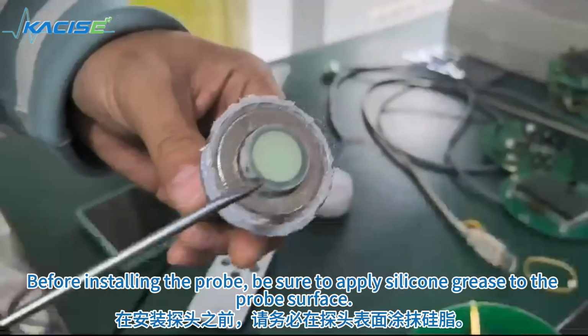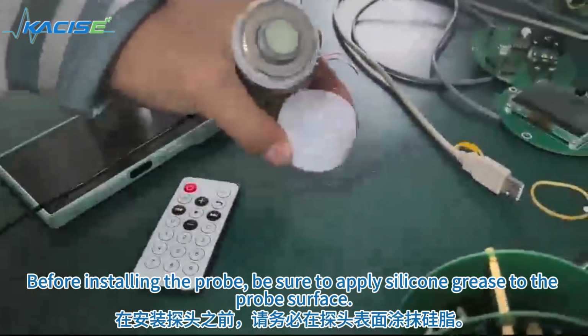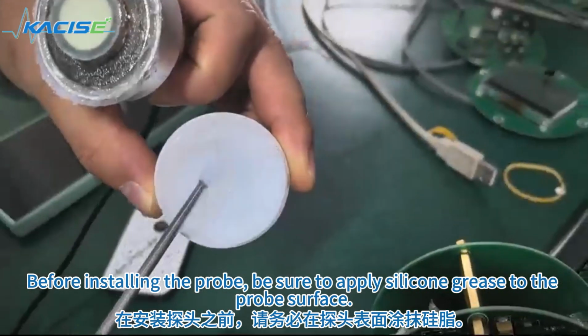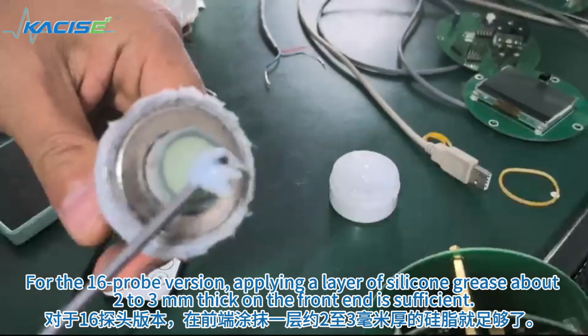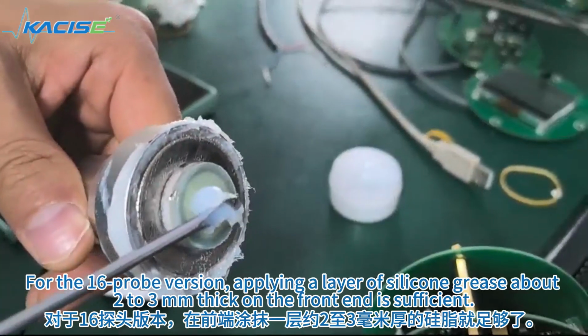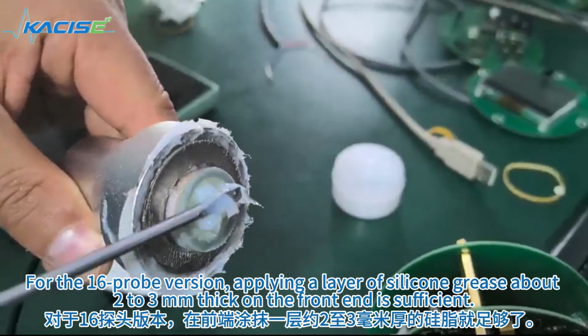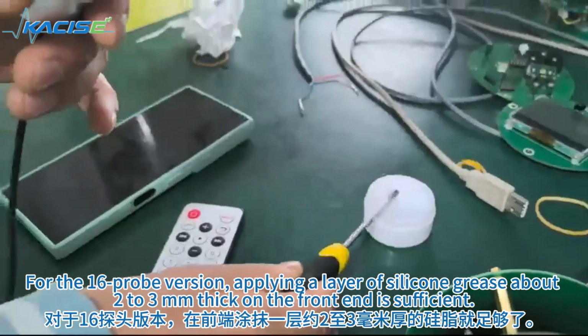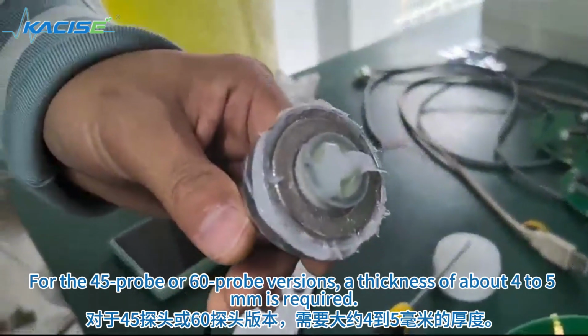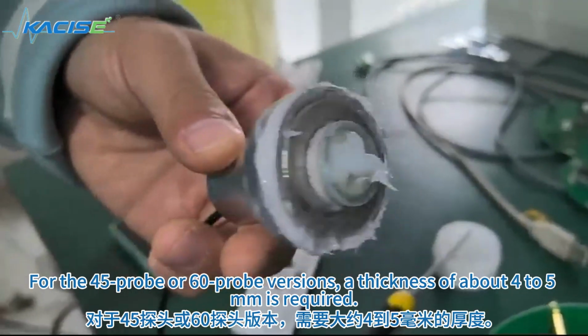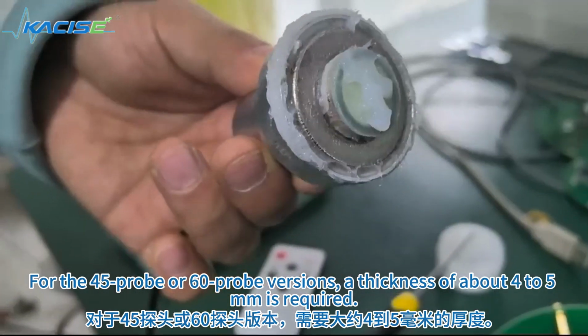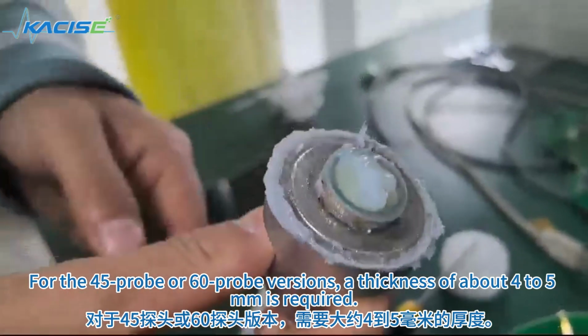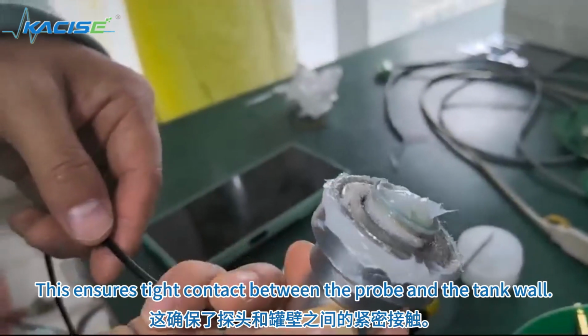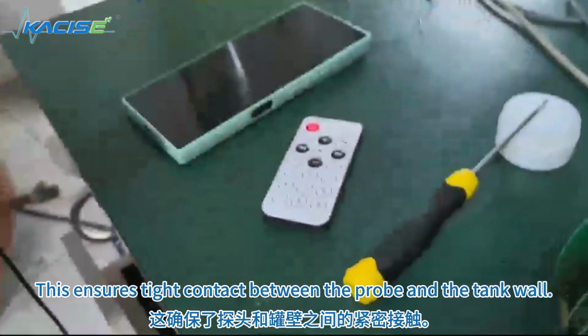Before installing the probe, be sure to apply silicone grease to the probe surface. For the 16-probe version, applying a layer of silicone grease about 2 to 3 millimeters thick on the front end is sufficient. For the 45-probe or 60-probe versions, a thickness of about 4 to 5 millimeters is required. This ensures tight contact between the probe and the tank wall.